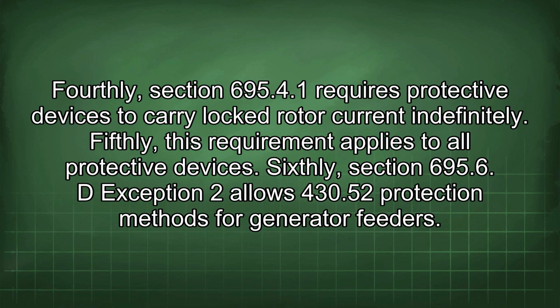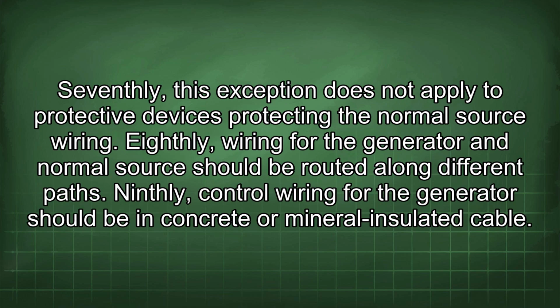Fourthly, Section 695.4.1 requires protective devices to carry locked rotor current indefinitely. Fifthly, this requirement applies to all protective devices. Sixthly, Section 695.6.D exception 2 allows 430.52 protection methods for generator feeders. Seventhly, this exception does not apply to protective devices protecting the normal source wiring.